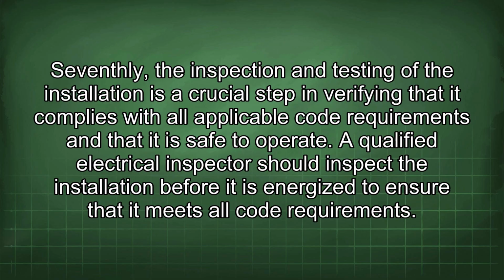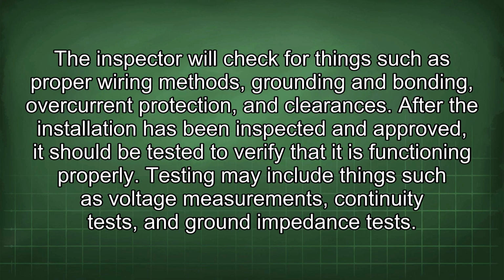Seventhly, the inspection and testing of the installation is a crucial step in verifying that it complies with all applicable code requirements and that it is safe to operate. A qualified electrical inspector should inspect the installation before it is energized to ensure that it meets all code requirements. The inspector will check for things such as proper wiring methods, grounding and bonding, overcurrent protection, and clearances. After the installation has been inspected and approved, it should be tested to verify that it is functioning properly. Testing may include things such as voltage measurements, continuity tests, and ground impedance tests.